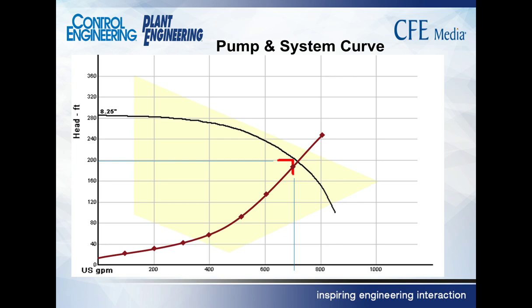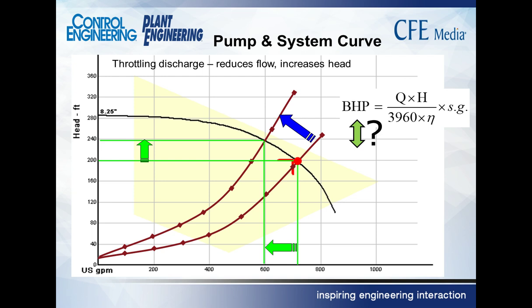What do we do? One thing you could do would be to close a discharge valve, called a throttle valve, and throttle the flow. When we close the discharge valve, we bend the system curve. There's our operating point. We bend the system curve back and up because we've introduced more friction, more head loss, into the system. Okay? What's the effect?